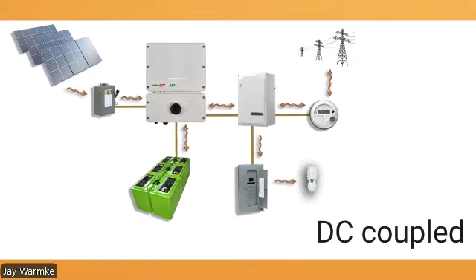So what you need is some sort of transfer switch. It could be built into the inverter or it could be separate. And it says, okay, the grid's down, I'm going to physically disconnect from the grid, and now I'm going to use our batteries and our solar array to run our loads. And you can run all your loads or some of the loads. Well, in the DC coupled system, logically, you've got solar power coming in, it's DC. Then you've got batteries and it's DC. And it all goes to the inverter and then it's converted to AC.